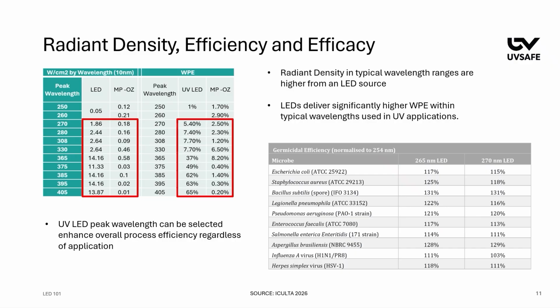Another benefit of an LED is that it can be designed towards specific pathogens, meaning if you were targeting, let's say, rotavirus, and that pathogen has a peak of 268 nanometers, don't quote me on that, I don't know exactly what the peak is, but you could use a 265 to 270 nanometer LED, which is very close to that peak, and align with that peak absorption range, where with legacy lamps, you're just stuck with what that chemistry produces, which is 254 nanometers. So that would mean you would actually have to apply a higher dose, which could potentially mean a higher input energy. That really comes down to the system wall plug efficiency and the different technologies, but ultimately what it means is that in that specific pathogen application, the LED would be more efficient.